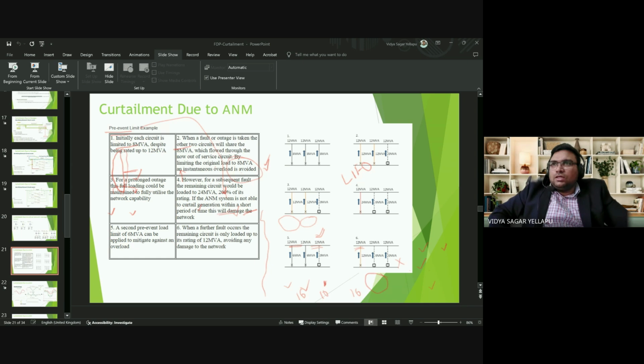In this case, if one of these circuits goes offline, then the available capacity with the others is 12 plus 12, 24 MVA. So if all these assets carry 24 MVA together, then there is no problem in the case of one of the assets failing. That is a pre-event limit set by this ANM. This is the case of n minus one, and in this case, with 8 MVA in pre-fault, all the situation is okay. But if it continues to do so, then in the case of another failure, one of the assets has to carry the total power, so it has to be 24 MVA, which again overloads this, which is not good.